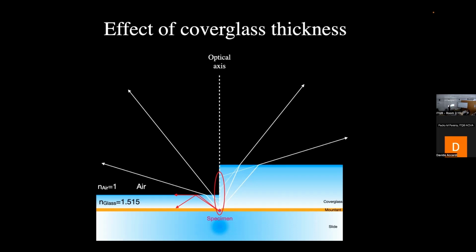And one thing that I didn't write here: always use cover slips that are 0.17 millimeters thick, plus minus 0.005 millimeters. Or you can also find them as 170 plus minus 5 micrometers. These are not just the number 1.5, but number 1.5 highly selected.